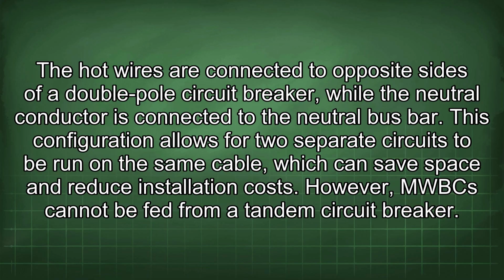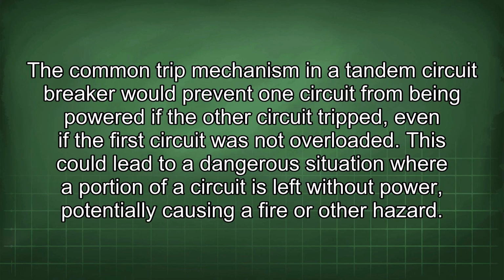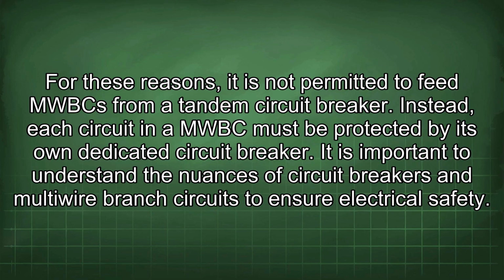However, MWBCs cannot be fed from a tandem circuit breaker. The common trip mechanism in a tandem circuit breaker would prevent one circuit from being powered if the other circuit tripped, even if the first circuit was not overloaded. This could lead to a dangerous situation where a portion of a circuit is left without power, potentially causing a fire or other hazard. For these reasons, it is not permitted to feed MWBCs from a tandem circuit breaker. Instead, each circuit in a MWBC must be protected by its own dedicated circuit breaker.